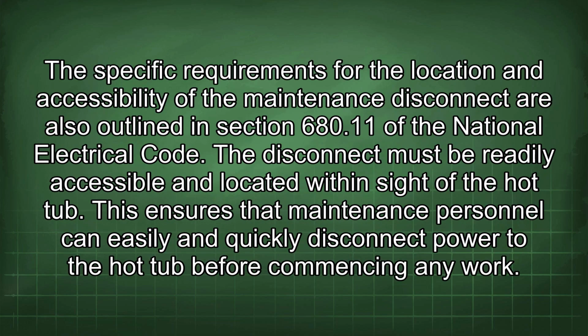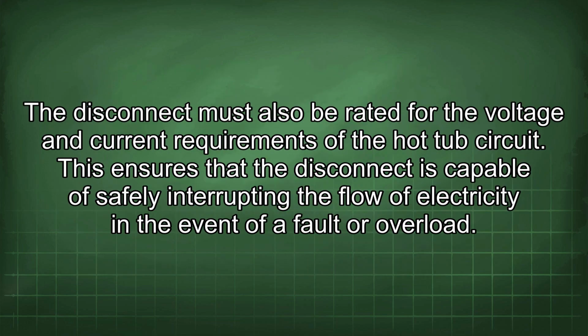The specific requirements for the location and accessibility of the maintenance disconnect are also outlined in Section 680.11 of the National Electrical Code. The disconnect must be readily accessible and located within sight of the hot tub. This ensures that maintenance personnel can easily and quickly disconnect power to the hot tub before commencing any work. The disconnect must also be rated for the voltage and current requirements of the hot tub circuit. This ensures that the disconnect is capable of safely interrupting the flow of electricity in the event of a fault or overload.